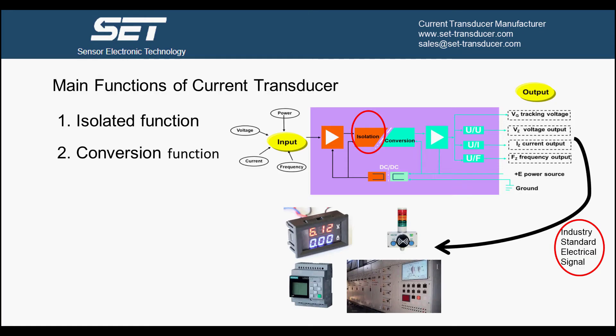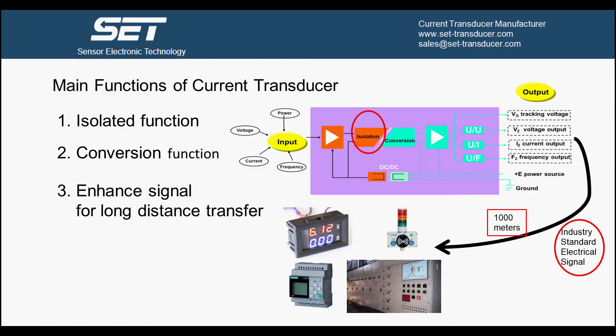Third: enhance signal for long distance transfer. Current transducer can enhance weak current to an easy-to-receive standard signal, so the output signal can be transferred for a long distance, such as 4 to 20 mA signal can be transferred up to 1000 m.